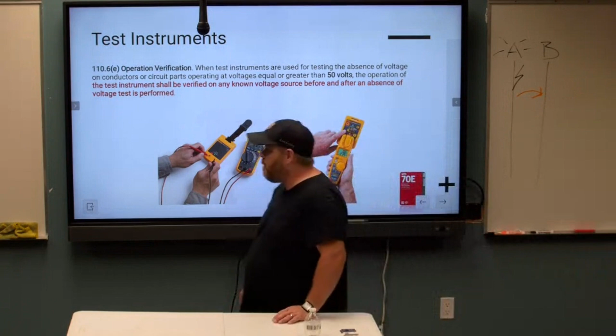I know that with 14-3, both travelers will have that induction, that false positive on it. Yep, exactly. Two conductors in a conduit, two conductors in a cable. Can happen. So whoever said they don't give you accurate readings is absolutely correct. But if they're working right, it's going to give you a false positive.